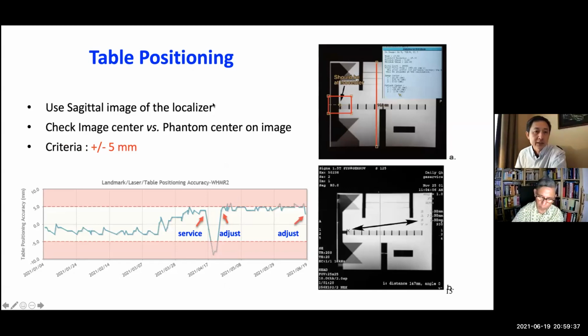So one of the tests is table position accuracy. This is included in the weekly testing and also annual and also acceptance testing. This is very simple. We just test the axial laser. So basically here is the center in the SI direction, the center of the phantom. If we laser a landmark at the center of the phantom, then here should be the center of the image.